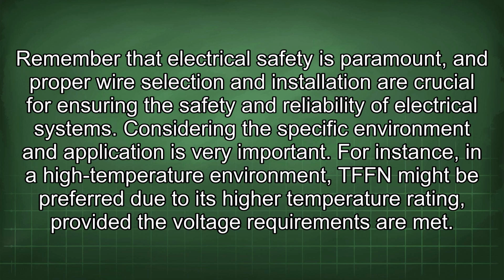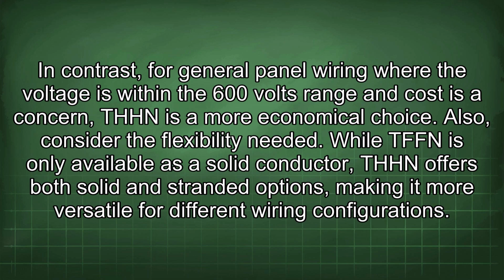For instance, in a high-temperature environment, TFFN might be preferred due to its high temperature rating, provided the voltage requirements are met. In contrast, for general panel wiring where the voltage is within the 600 volts range and cost is a concern, THHN is a more economical choice. Also, consider the flexibility needed. While TFFN is only available as a solid conductor, THHN offers both solid and stranded options, making it more versatile for different wiring configurations.